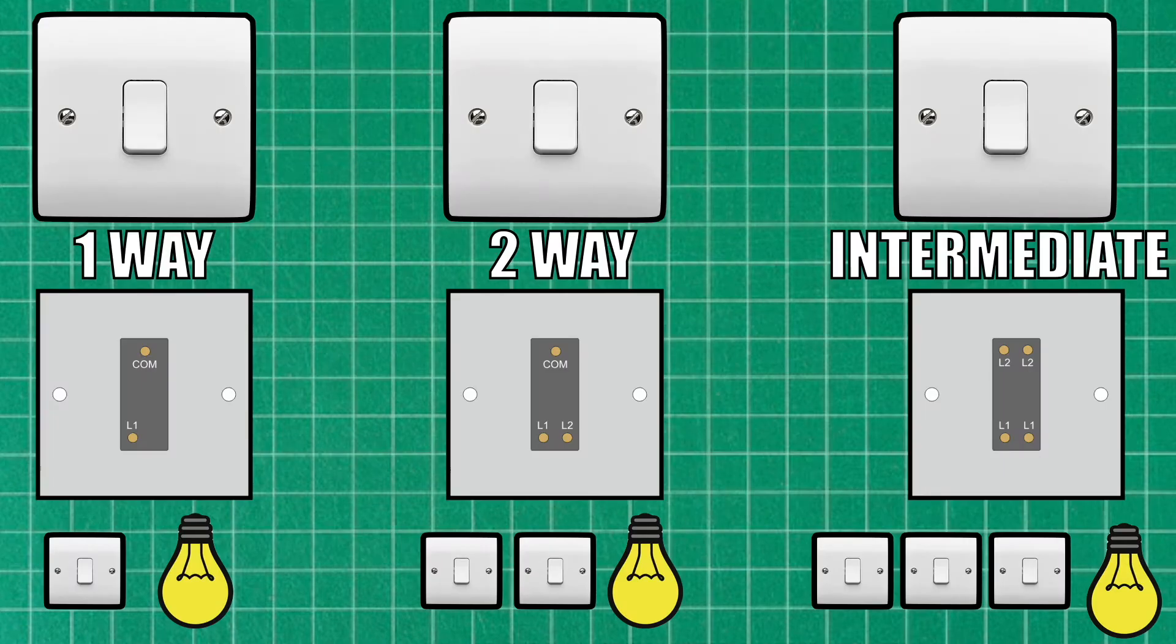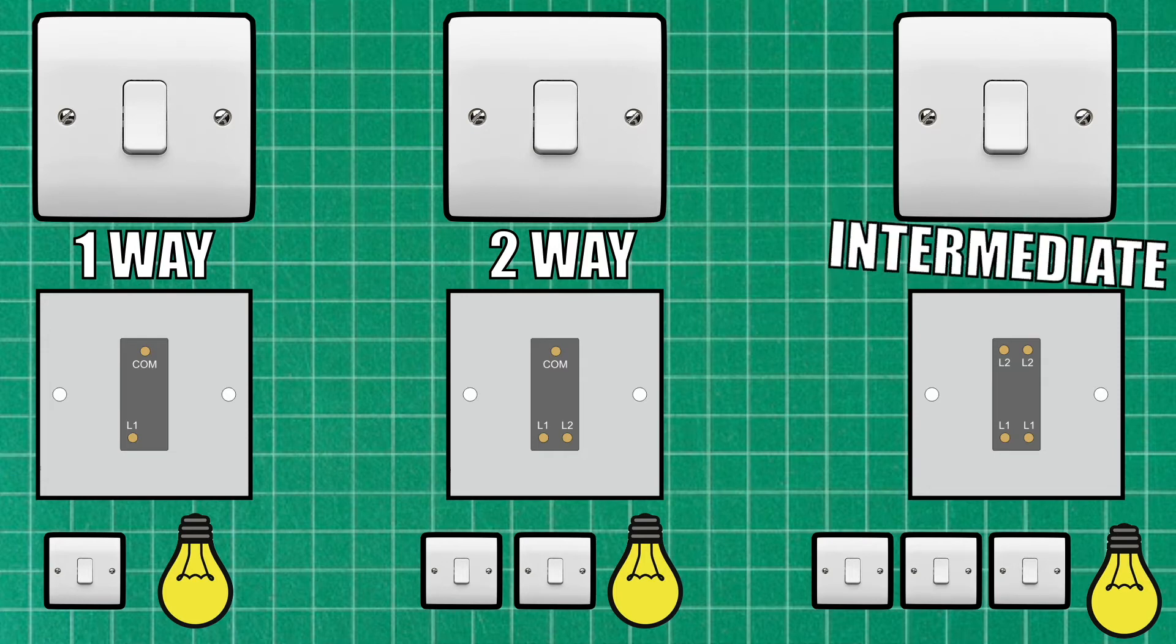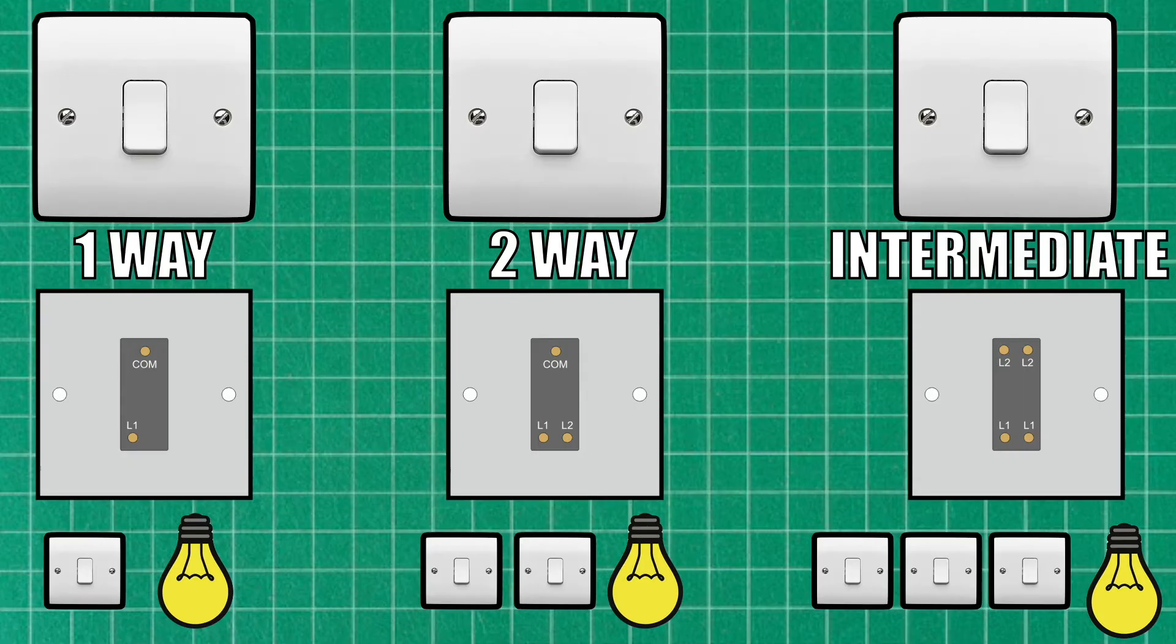So now if we take a look at these three switches, they all look the same from the front - they're all one gang switches. However, as you can see from the backs of these switches, they're different. So the one-way switch has two brass terminals, a common and an L1, and it allows us to connect one switch to one light. The two-way switch has three brass terminals at the back: a common, an L1, and an L2, and so this allows two switches to control that same light. And the intermediate switch has four brass terminals at the back and allows you to connect three or more switches to the same light.